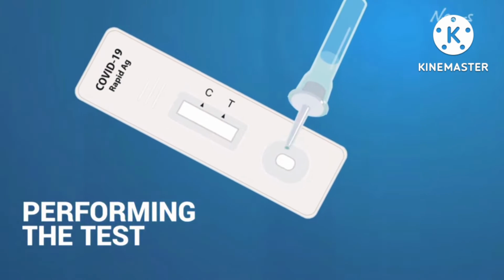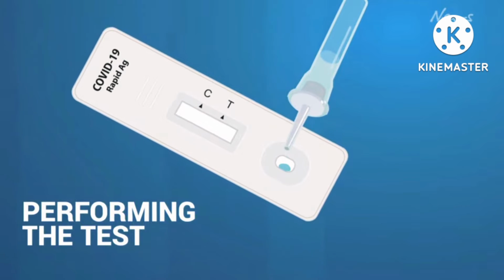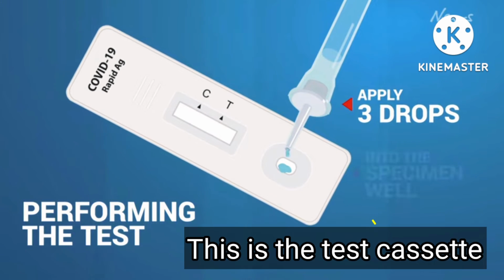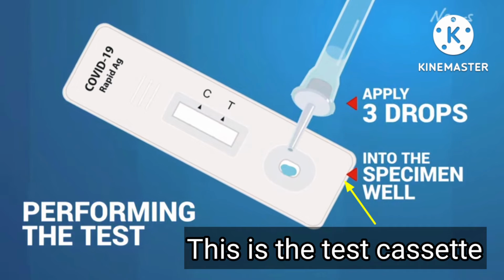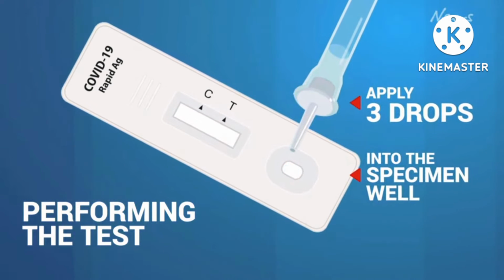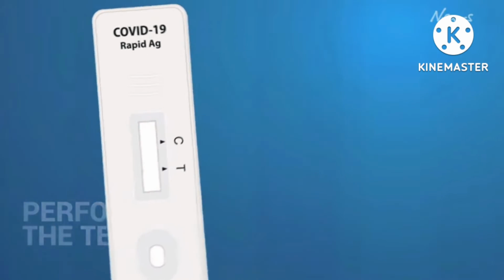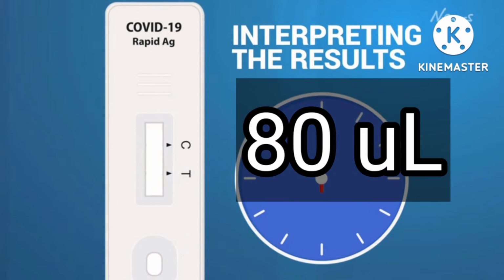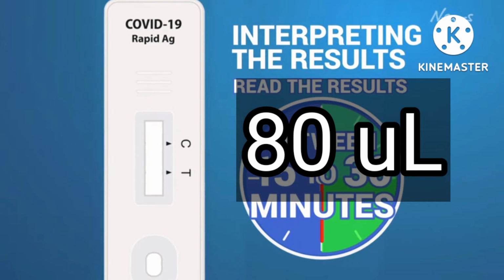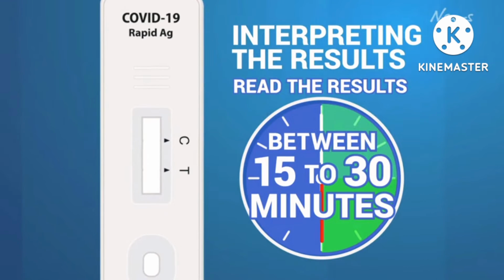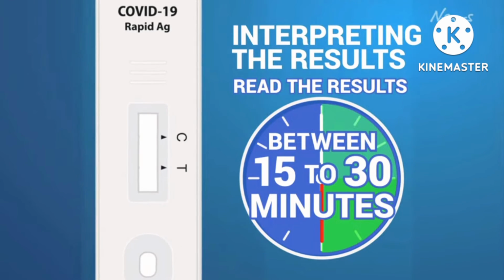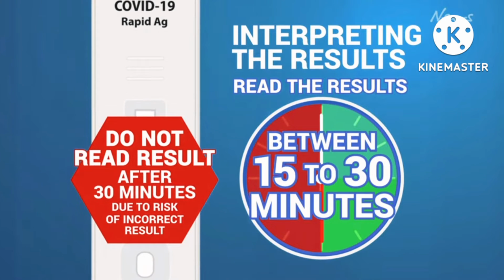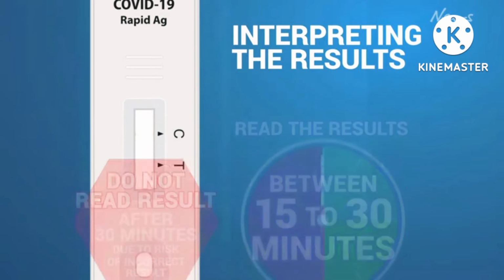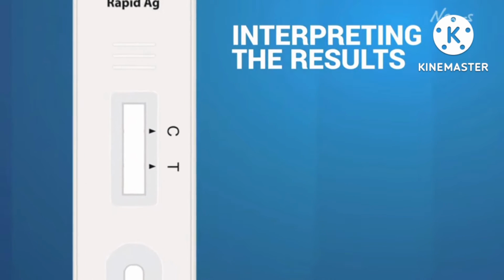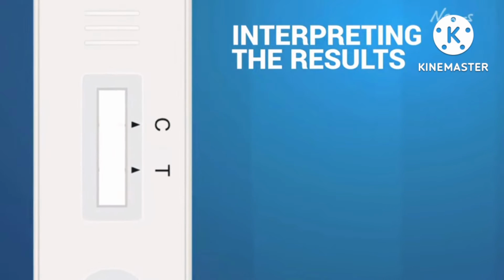Next, you remove a test cassette from the sealed pouch by tearing at the notch and place it on a level surface. Unscrew the small cap at the top of the extraction tube and add 80 microliters, or about 3 to 4 drops, of processed specimen to the sample well, and you may start the timer. Wait for 15 to 20 minutes and read the results. Please do not read results after 30 minutes. That is to avoid false positives.